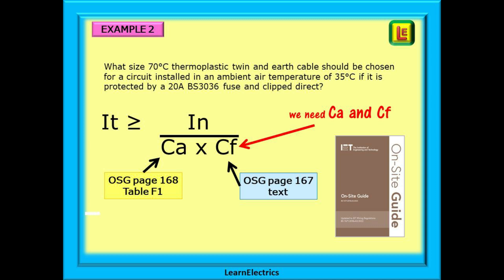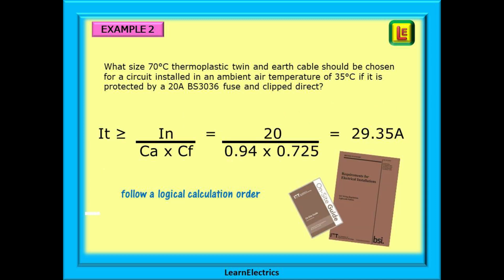CF, the fuse factor is only applied for BS3036 rewireable fuses and this is 0.725. This is because BS3036 fuses have a bigger fusing factor than other fuses and we need to allow for this. For all other fuses we use a factor of 1 which means that we can ignore it. Here is our calculation. 20 on the top and 0.94 multiplied by 0.725 on the bottom.